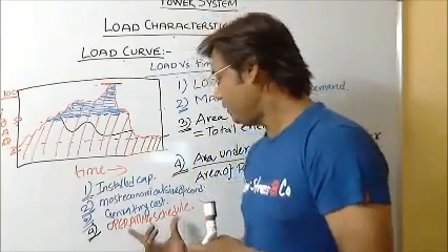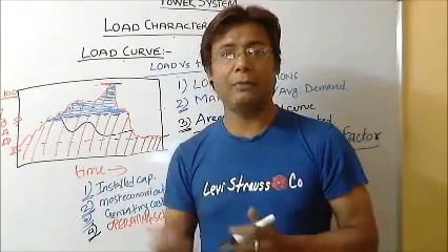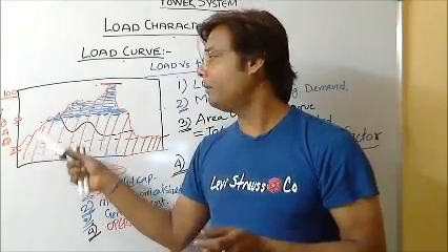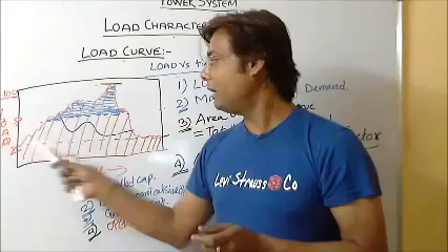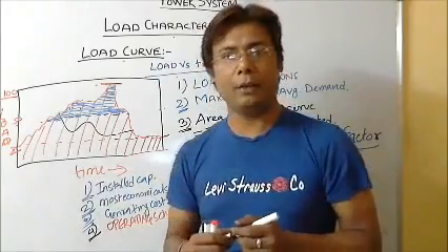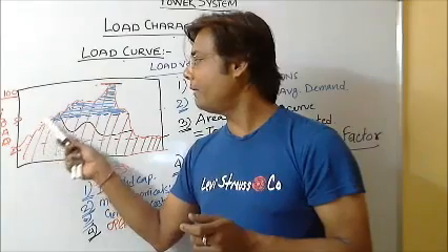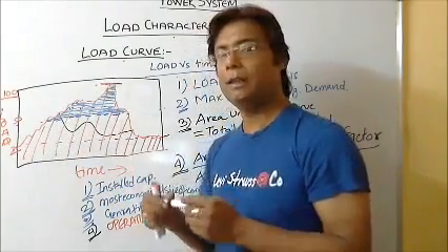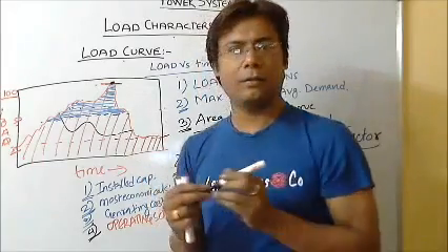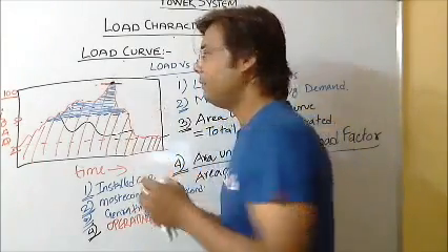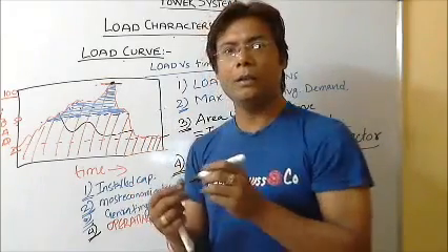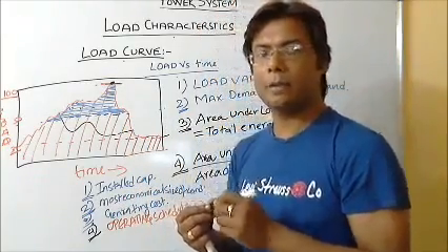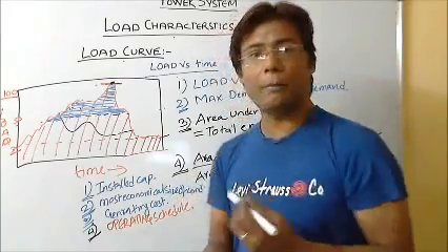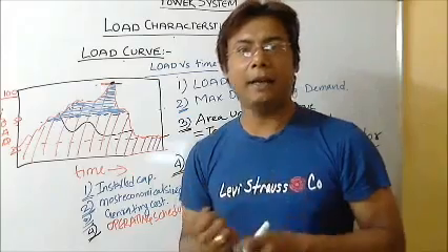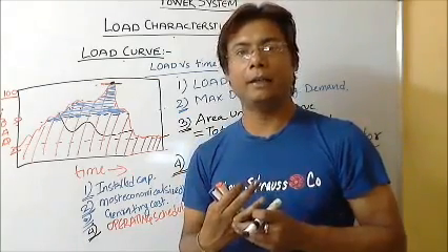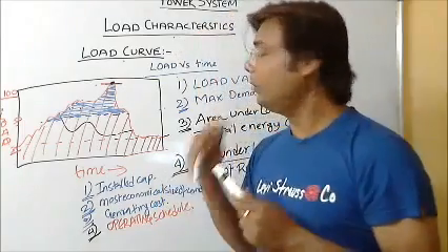So operating schedule - when I am talking about the 10 into 10 megawatt system, at that time I will be switching on the system when they are required. At least 3 would be always present if 10 into 10 megawatt system is concerned, and then 4, 5, 6, so on until all 10 will be under working condition at my peak load. As the load goes down, I can have removal of my generators from the system. So I can have the operating schedules in such a way that the demand and fulfillment of the demand is balanced. That will be the load curve.